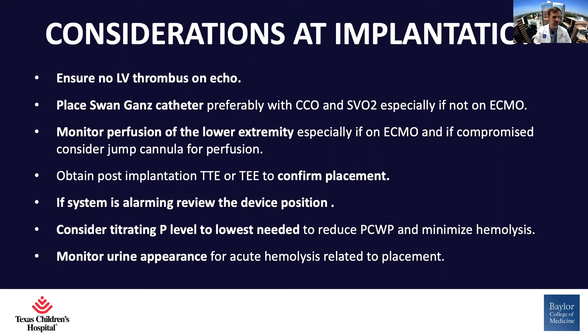The proper positioning of the device is essential. If the device is not in the right place, it will create suction events, it will create increased hemolysis, and it will be very prone to dislocation or malposition, causing more problems rather than benefit for our patients. So, the typically recommended position of the device, I'm showing you a little bit of an animated echo here with a transesophageal echo picture, but more commonly you will be utilizing a transthoracic echo. Typically it's done through three measurements and taking an average, with a recommended position for the 2.5 and CP devices to be around 3.5 centimeters below the aortic valve, and for the 5.0 and 5.5 devices to be around 5 centimeters below the aortic valve.